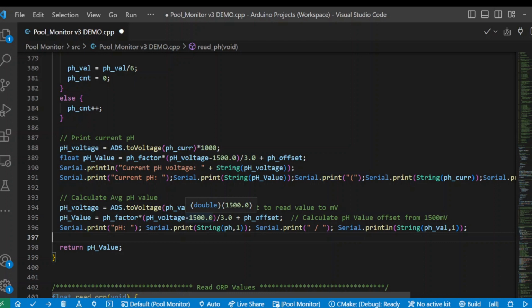So here I'm taking my measured value, and as I said, I'm offsetting it from pH 7. So I'm deducting 1500 millivolts, and then I'm also adding the pH offset I had previously calibrated and multiplying with the pH factor. So in the end, this variable here, pH value, will hold my average pH value. In this case, since I'm measuring I think it was every 3 seconds, or every 5 seconds it was, and I'm covering 10 values, it will take a minute to calculate the average value.